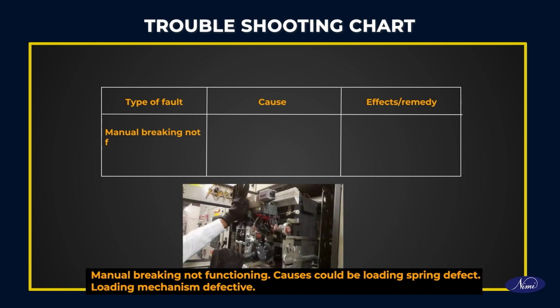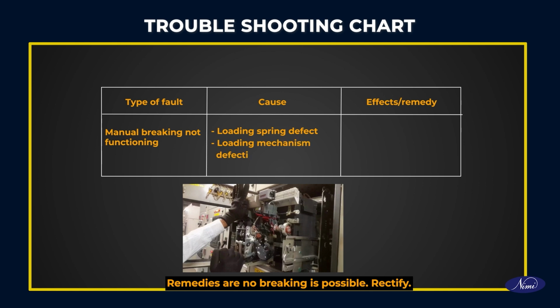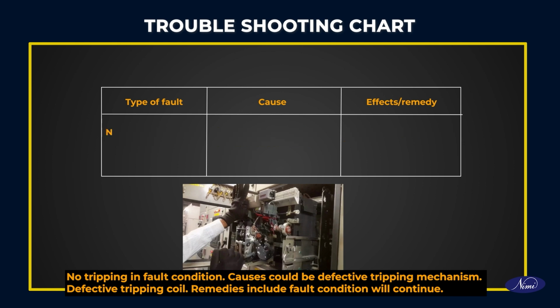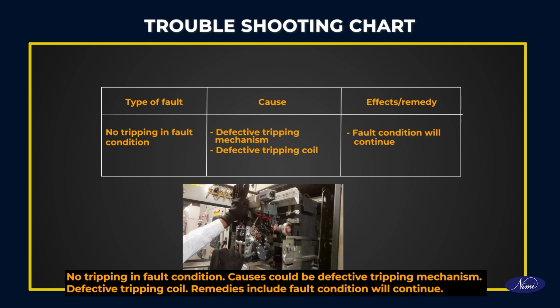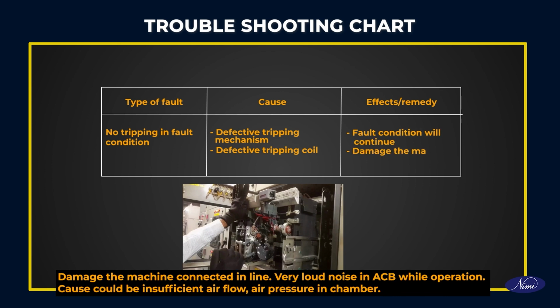Manual breaking not functioning. Causes could be loading spring defect, loading mechanism defective. Effect: no breaking is possible. Remedy: rectify. No tripping in fault condition. Causes could be defective tripping mechanism, defective tripping coil. Effect: fault condition will continue and may damage the machine connected in line.